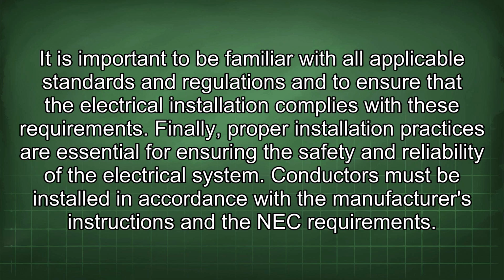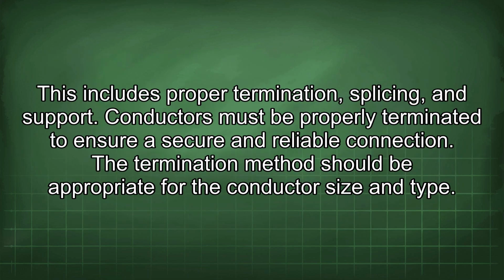Finally, proper installation practices are essential for ensuring the safety and reliability of the electrical system. Conductors must be installed in accordance with the manufacturer's instructions and the NEC requirements. This includes proper termination, splicing, and support. Conductors must be properly terminated to ensure a secure and reliable connection. The termination method should be appropriate for the conductor size and type.